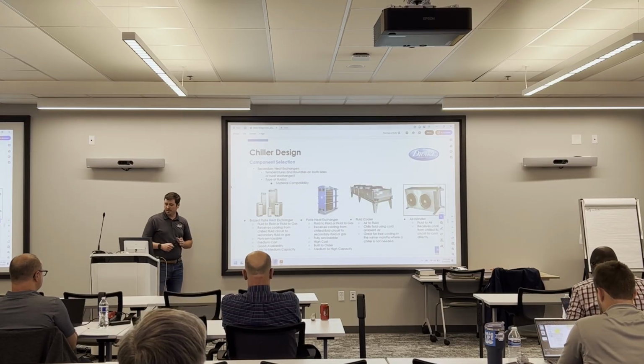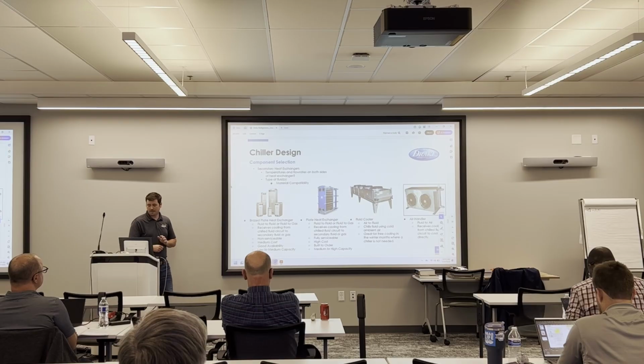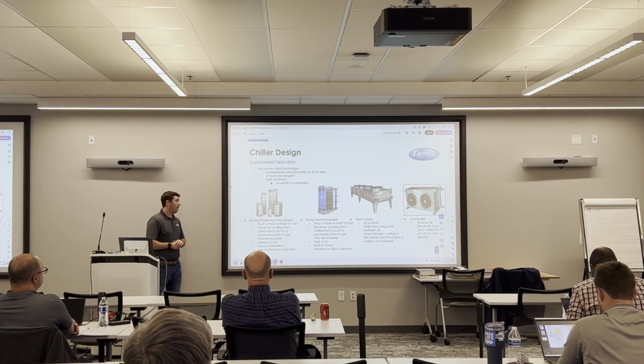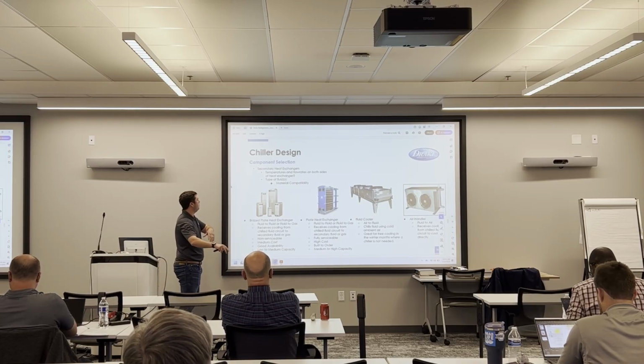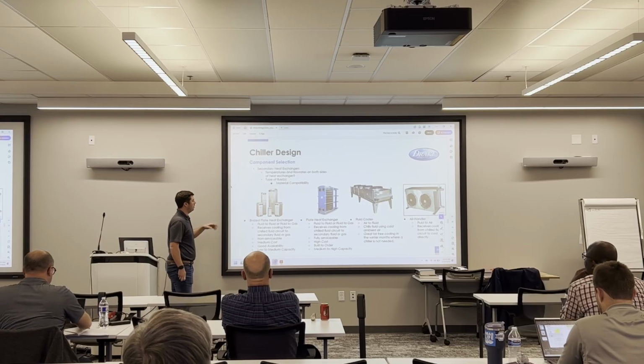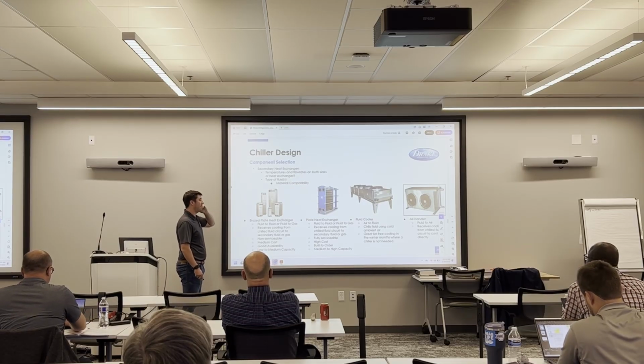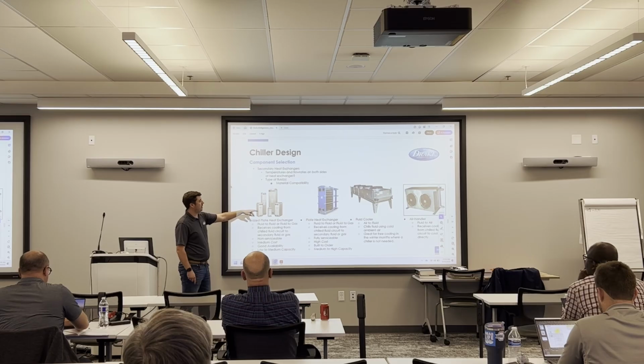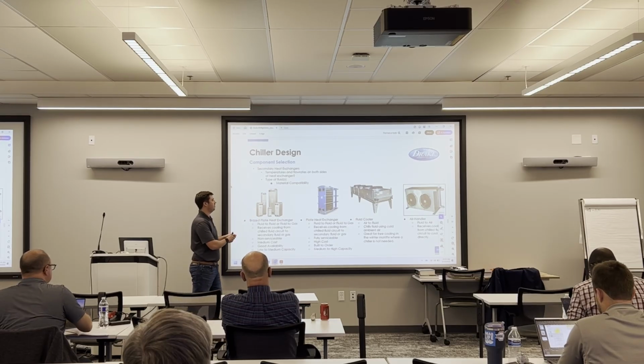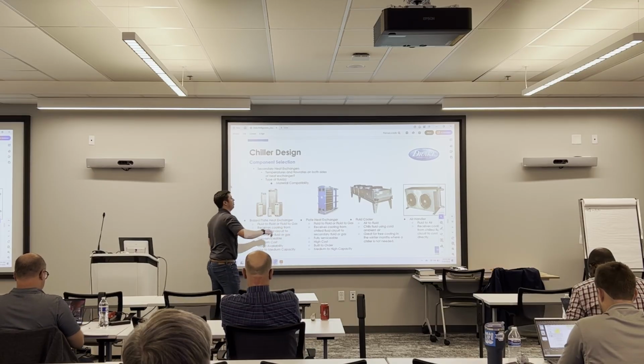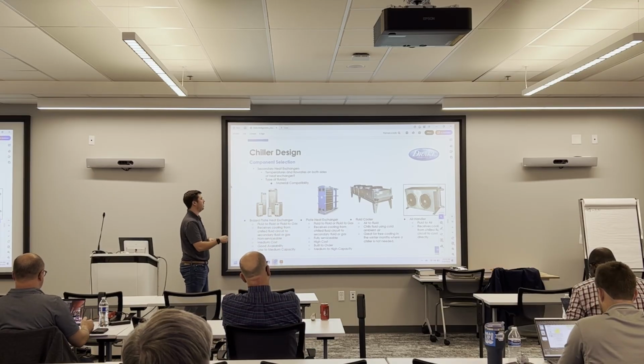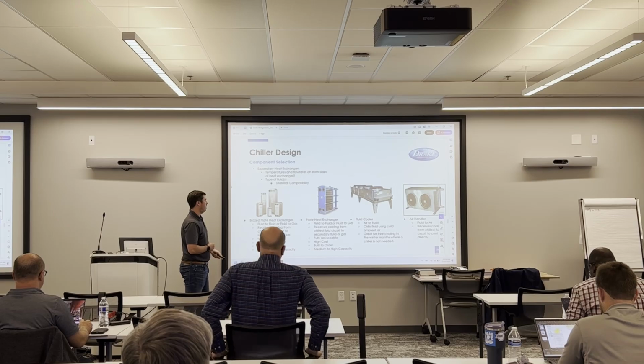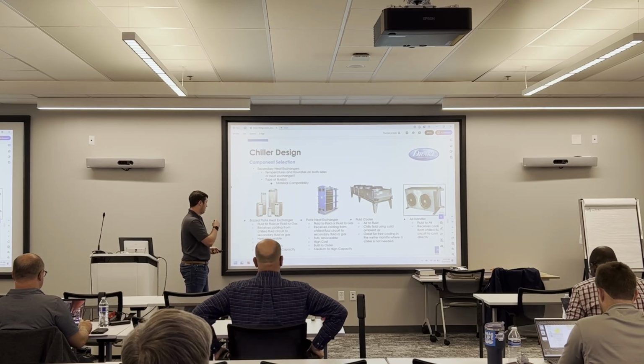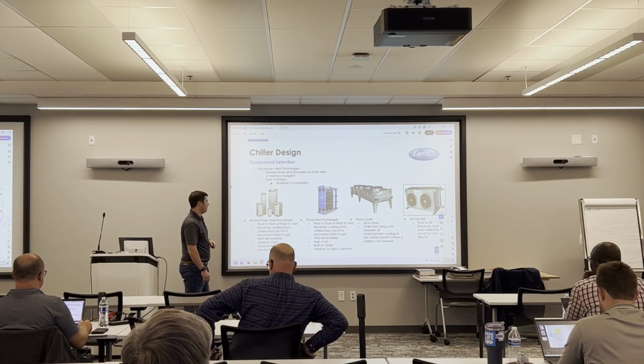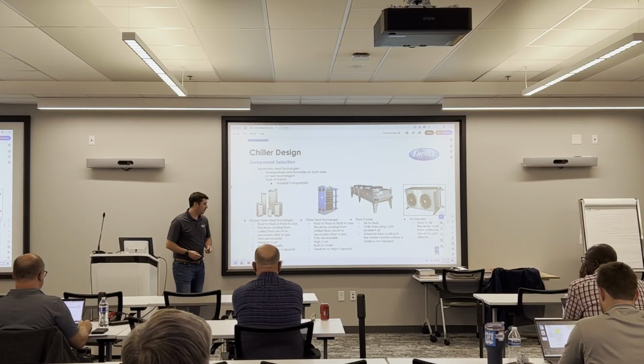Just talking about some secondary heat exchangers on our hydronic circuit, all different styles here. If you have a secondary cooling medium, like if you want to cool water with glycol, you do a brazed plate heat exchanger, which we already talked about. There are plate heat exchangers available as well. They're really good for gas cooling, and they're fully serviceable. You can unbolt this plate heat exchanger, pull the whole thing out, clean each plate individually, and put it back together again. Compared to the brazed plates, you're going to have a higher cost for the plate and frame. They're generally built to order. They're good for medium to high capacities.